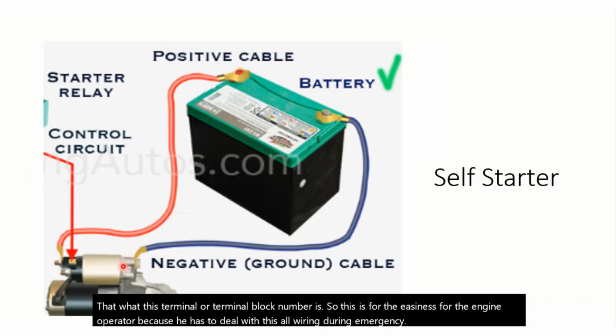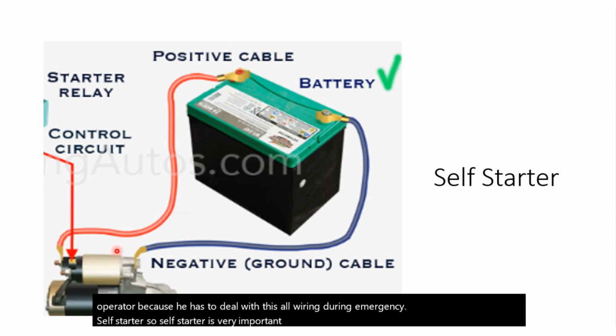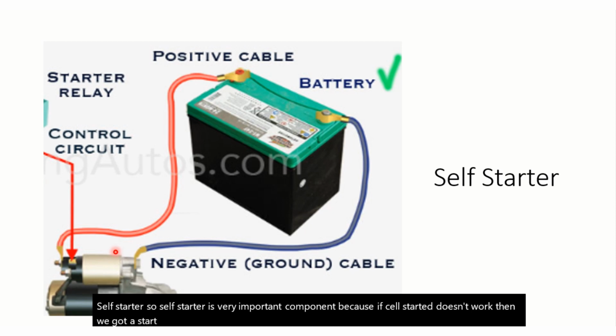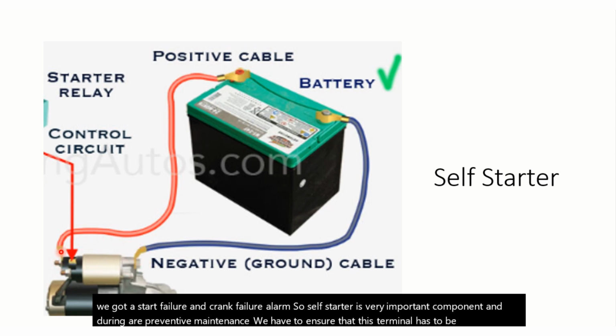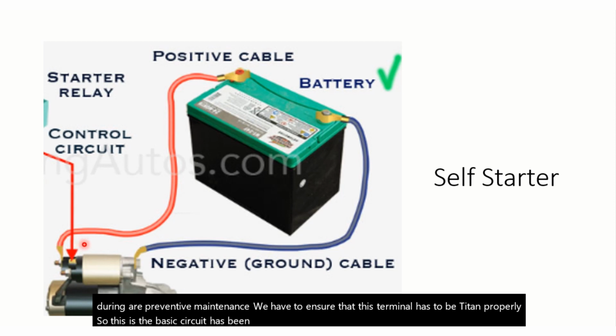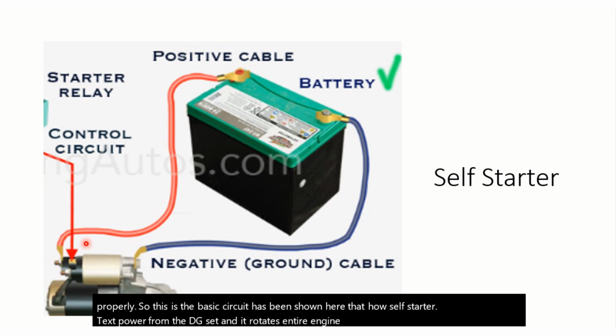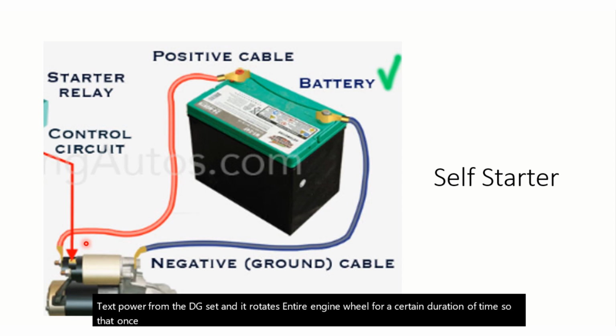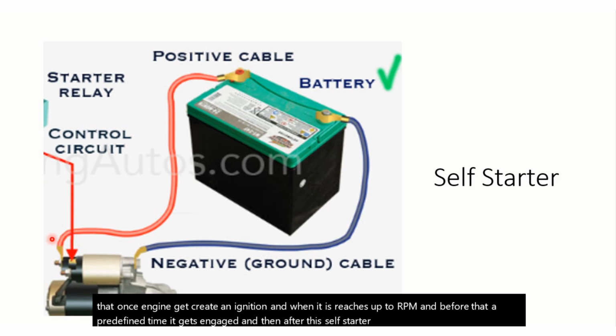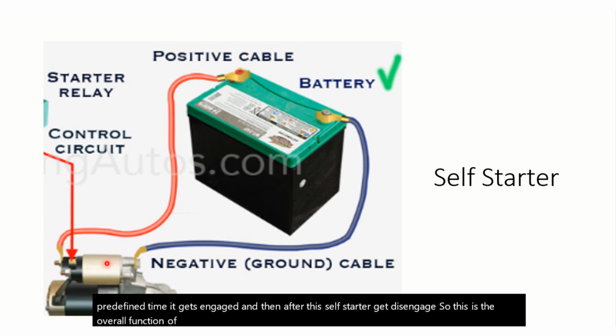Now the self starter. The self starter is a very important component, because if it doesn't work, then we get a start failure and crank failure alarm. During our preventive maintenance we have to ensure that this terminal is tightened properly. This is a basic circuit showing how the self starter takes power from the DG set, and rotates the entire engine wheel for a certain duration, so that once the engine creates ignition and reaches a certain RPM, before a predefined time, it gets disengaged. This is the overall function of the starter, to provide the starting torque to the engine.